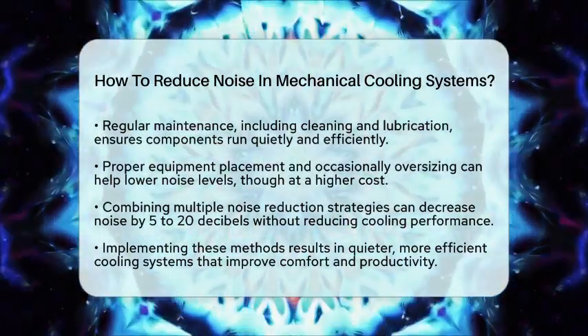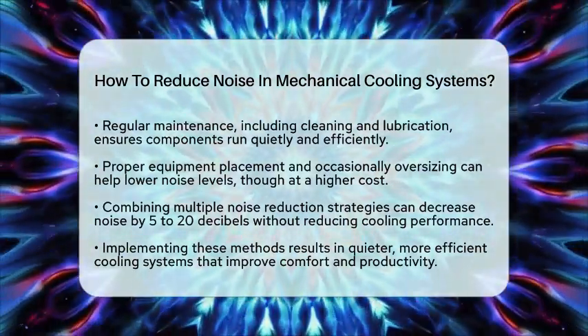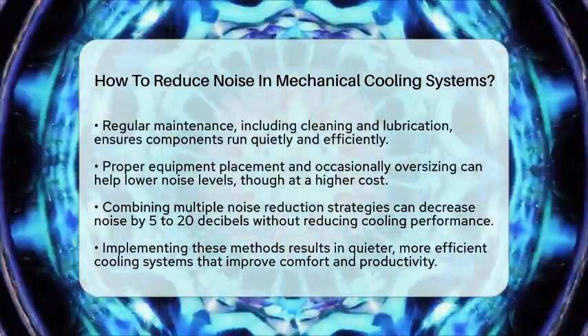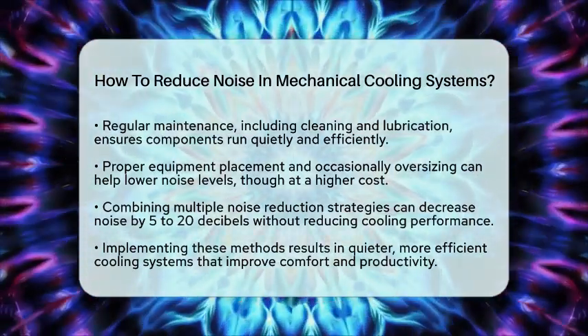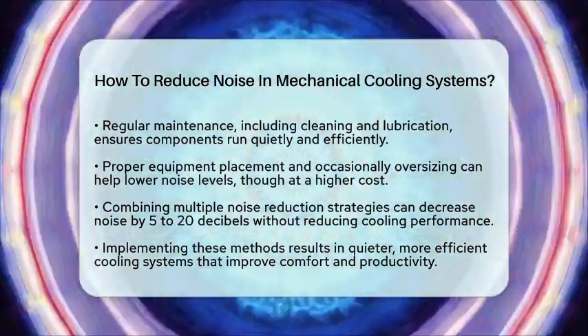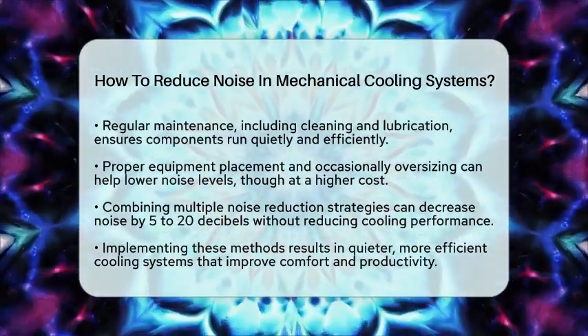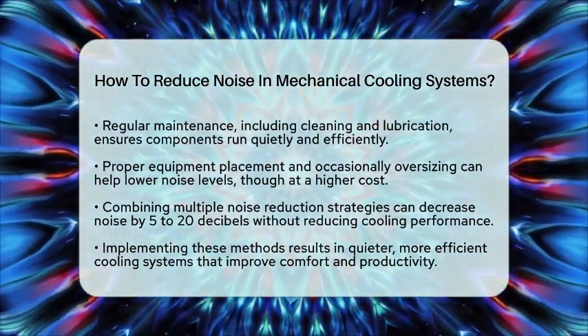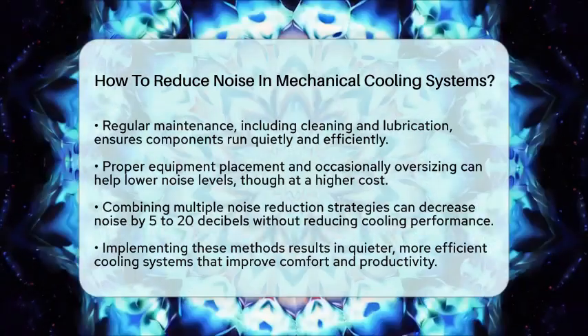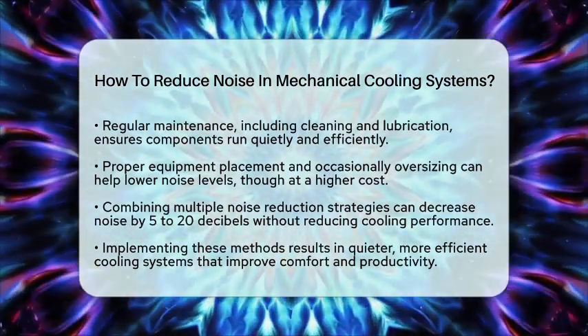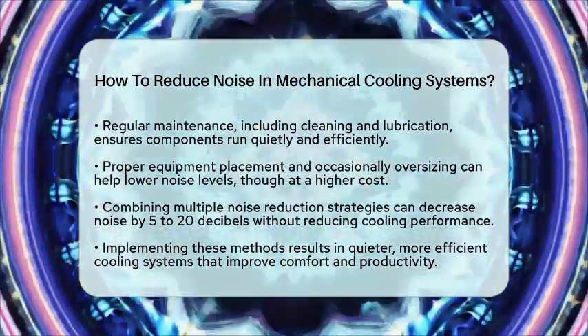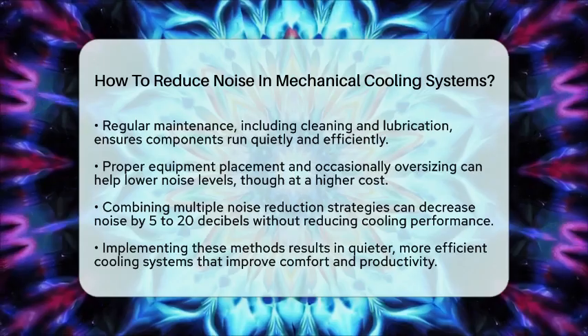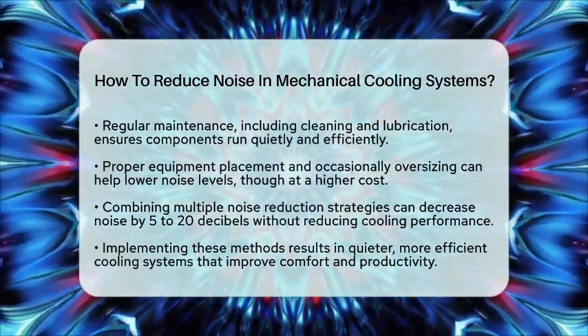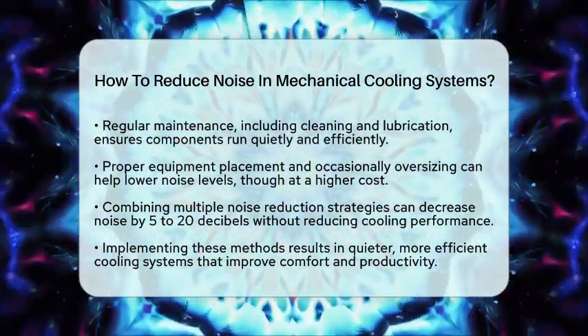In practice, combining these methods can reduce noise levels by 5 to 20 decibels without sacrificing cooling capacity. For example, adding damping materials and aerodynamic fan modifications can make a noticeable difference. Using variable frequency drives not only cuts noise but also lowers power bills. Installing acoustic barriers is effective but should be balanced with ventilation needs.